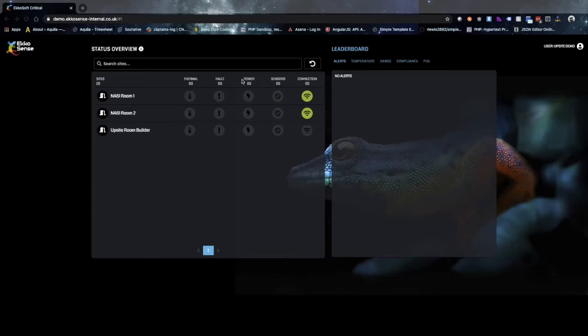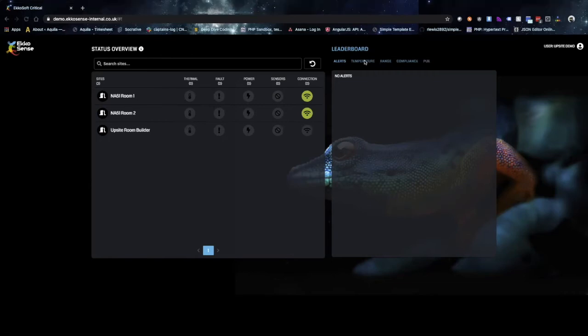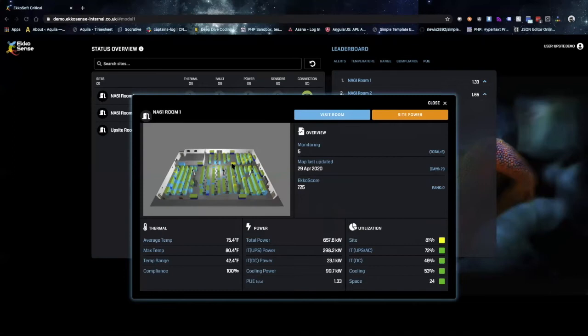Then you'll see the leaderboard. So for example, you'll see temperatures, which are the average inlet temperatures in this room. Then you'll see the range, which is the delta between the highest intake temperature and the lowest intake temperature in the room. Compliance level, which is based off of ASHRAE recommendations. And then finally, you'll see PUE for these rooms. Then you can go ahead and click on one and get some general details about this room. So first thing you'll see is the digital twin, so you can see what the room looks like.